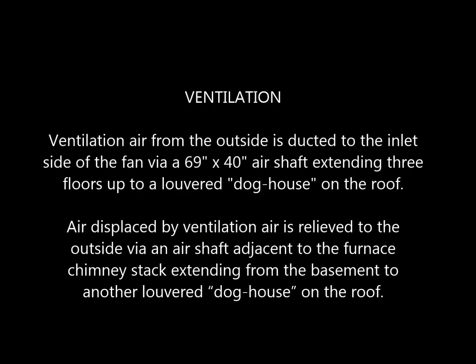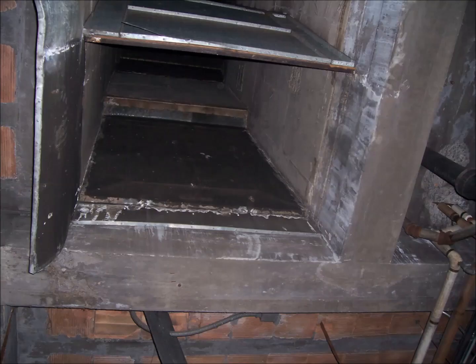Ventilation air from the outside is ducted to the inlet side of the fan via a 69-inch by 40-inch air shaft extending 3 floors up to a louvered doghouse on the roof. Air displaced by ventilation air is relieved to the outside via an air shaft adjacent to the chimney stack extending from the basement to another louvered doghouse on the roof. Here is a look up in the vertical shaft that is split into two, one side for supply air going up and the other side for outside air coming down.